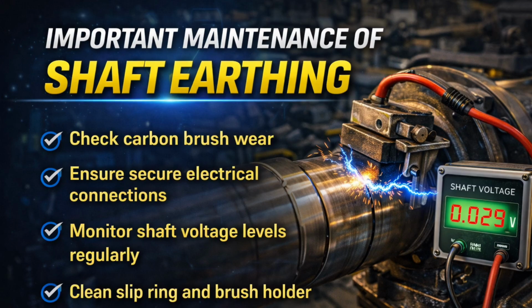Secure electrical connections. Next, inspect the electrical connections, including the earthing cables and red wires. Loose or corroded connections can prevent proper current flow, creating unsafe voltage on the shaft. Make sure all connections are tight, clean, and properly insulated. This step is crucial to prevent sparks, reduce resistance, and ensure the earthing path works effectively.